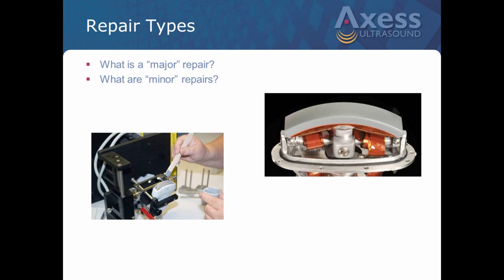Okay, repair types. Again, I said we go through major and minor repairs, kind of what those mean, if you're not familiar. Major repairs, and this is kind of an industry standard, we're talking about the array replacement, replacement of the entire cable. Sometimes some of you that are having probes repaired now may have run across a cable retermination, which is essentially rewiring the array. Electronic repairs, and most TEEs fall into that major area.